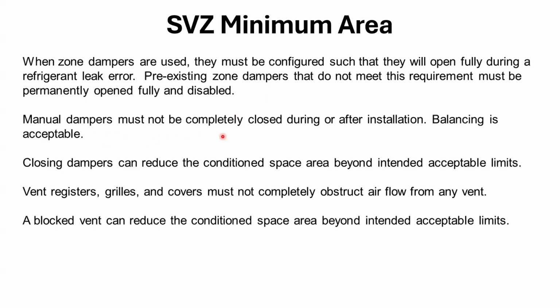Manual dampers must not be completely closed. Balancing is acceptable. Closing the dampers can reduce conditioned space area beyond the limits. Vent registers, grills, and covers must not completely obstruct airflow from any vent. And yeah, this is all in the install manual too, all of this talking about the dampers and everything. A blocked vent can reduce the conditioned space area beyond intended acceptable limits, right? So just all requirements on that.